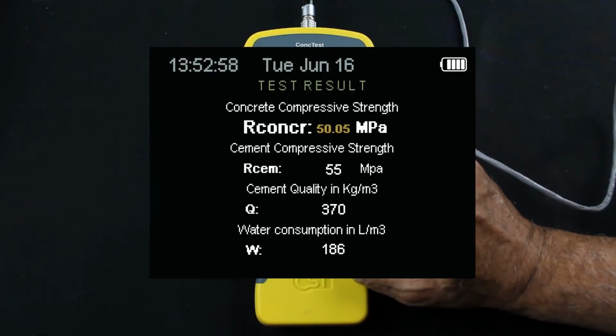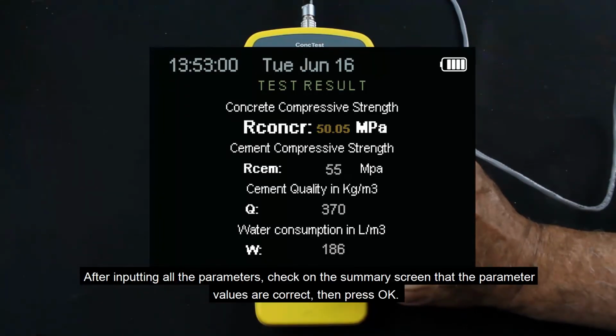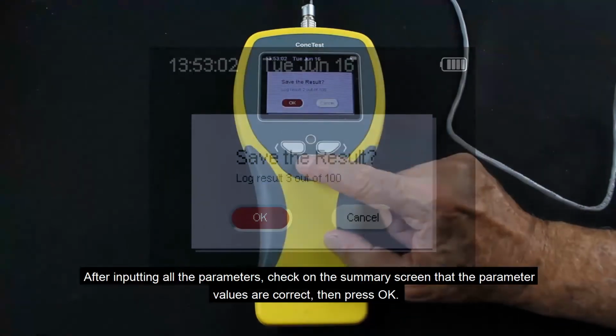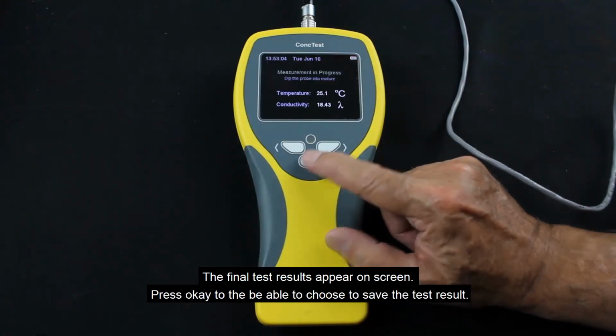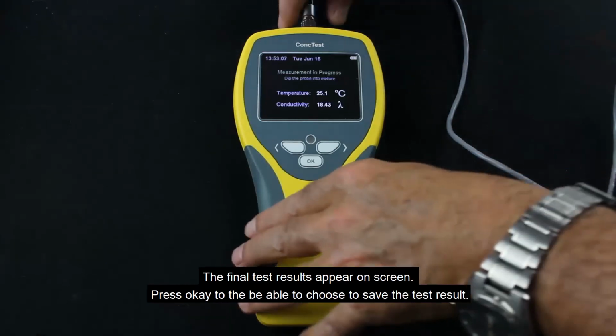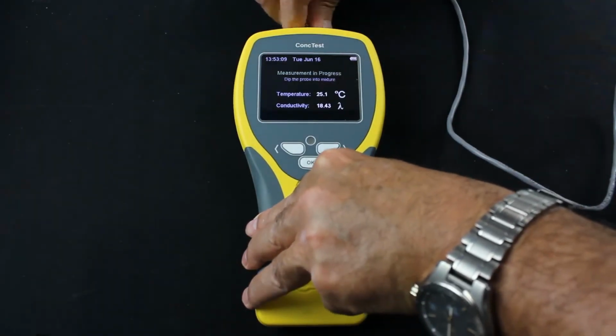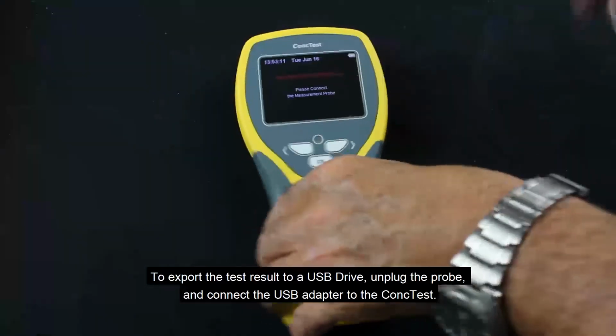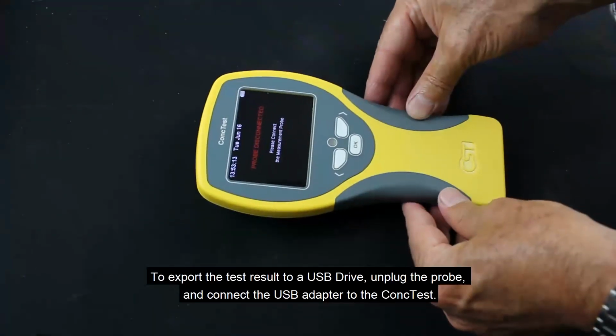user manual. After inputting all the parameters, check on the summary screen that the parameter values are correct, then press OK. The final test results appear on screen. Press OK to be able to choose to save the test result. To export the test result to a USB drive, unplug the probe and connect the USB adapter to the ConcTest.